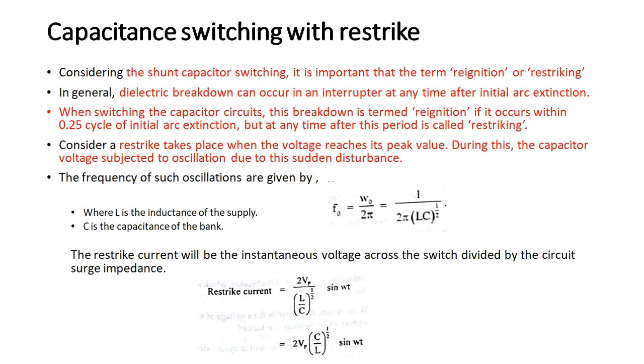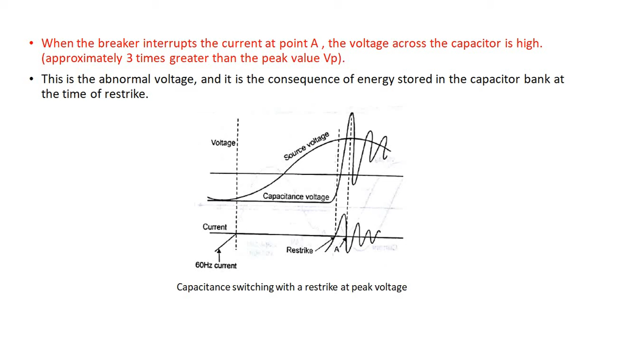When the breaker interrupts current at point A, the voltage across the capacitor is high, approximately 3 times the peak value. The abnormal voltage is a consequence of energy stored in the capacitor bank up to the time of restrike. The diagram represents the source voltage and the capacitor discharge voltage. The next one is the current in the oscillation, a sinusoidal waveform. Then the capacitance switching with a restrike at peak voltage.